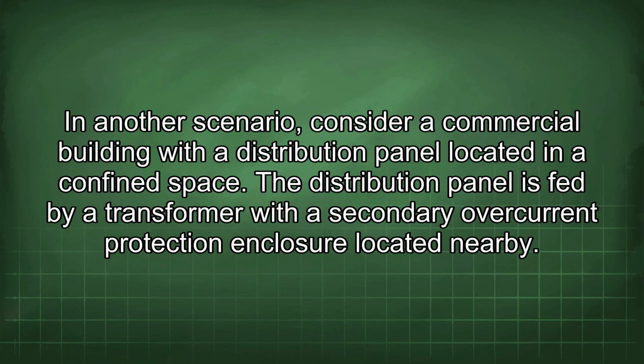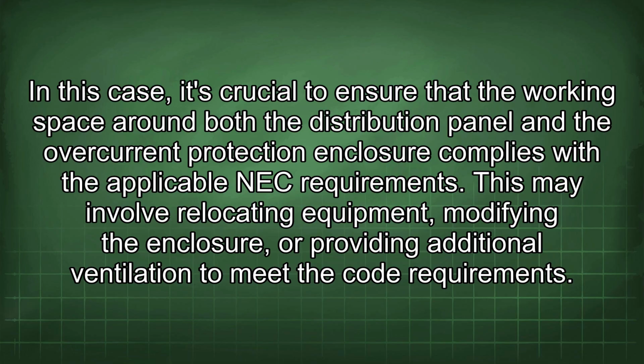This ensures that qualified personnel can safely access and maintain the motor control equipment. In another scenario, consider a commercial building with a distribution panel located in a confined space. The distribution panel is fed by a transformer with a secondary overcurrent protection enclosure located nearby. In this case, it's crucial to ensure that the working space around both the distribution panel and the overcurrent protection enclosure complies with the applicable NEC requirements. This may involve relocating equipment, modifying the enclosure, or providing additional ventilation to meet the code requirements.